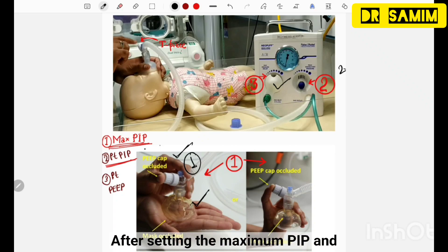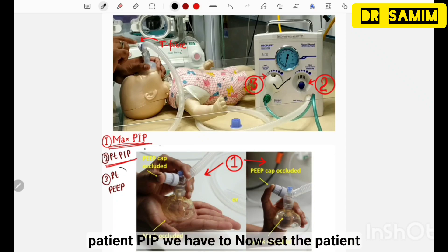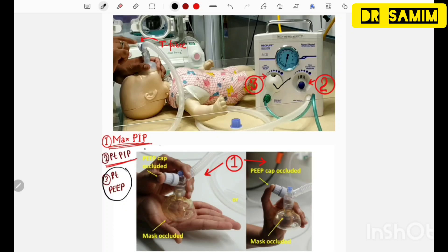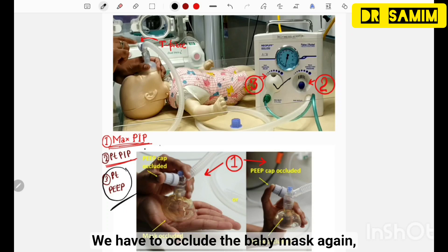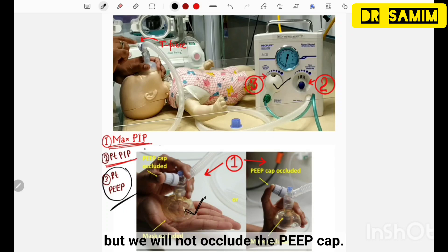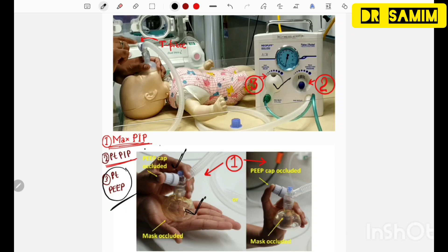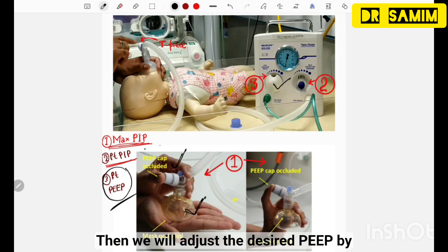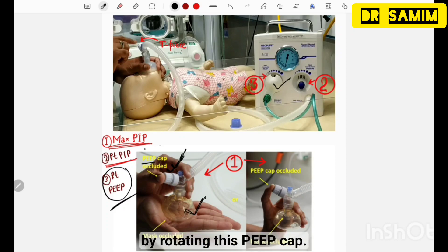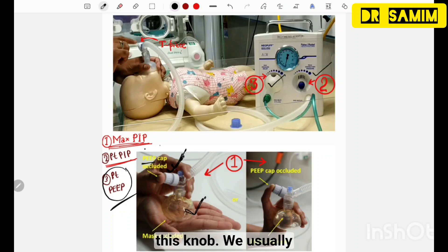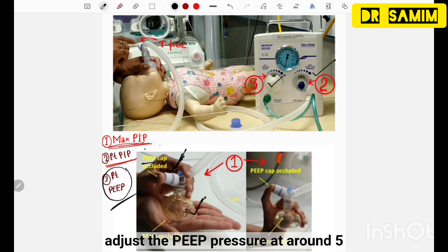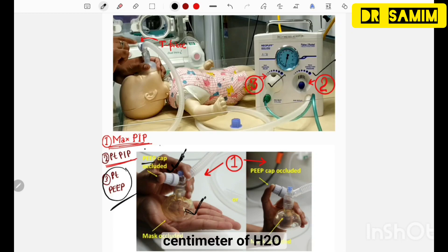After setting maximum PIP and patient PIP, we now set the patient PEEP. To set patient PEEP, first occlude the babymax again but do not occlude the PEEP cap. Then adjust the desired PEEP by rotating the PEEP cap, without touching the PIP control knob or the pressure release knob. We usually adjust the PEEP pressure at around 5 cmH2O.